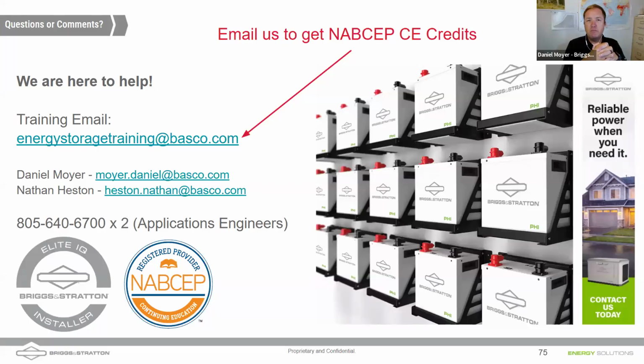So we adjusted maybe the bulk, float, and absorb voltages, and made sure we disabled the equalize because we don't want to fry the batteries. We also made sure that with the older inverters, maybe that 8,000 watt Radian, you can't adjust the discharge of the battery — if somebody turns on 8,000 watts worth of loads in the home, we need to make sure our batteries can supply the amps the inverter is calling for.